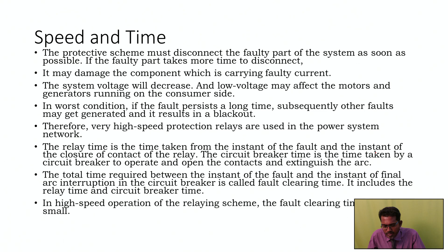Okay, that's a thing. The fourth one is that very high speed protective relays are used in power systems. The relay time is the time taken between the instant of fault and the instant of closure of the contact of the relay. The circuit breaker time is the time taken by the circuit breaker to operate, open the contact and extinguish the arc. So these are the definitions given for the circuit breaker time and the relay time. Okay, the first three lines say how fast it has to work.